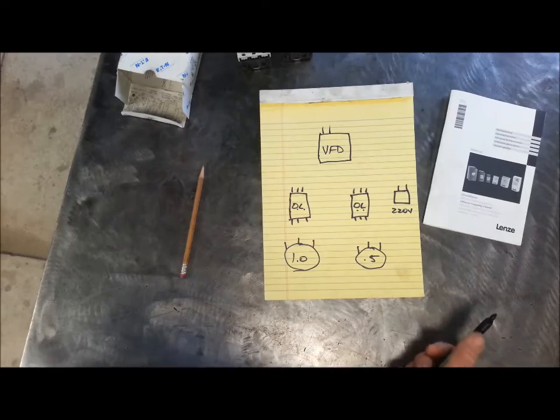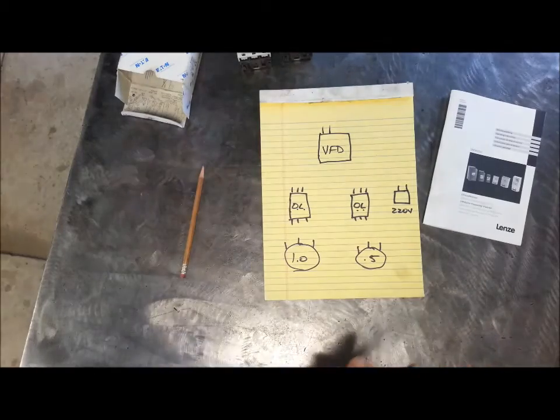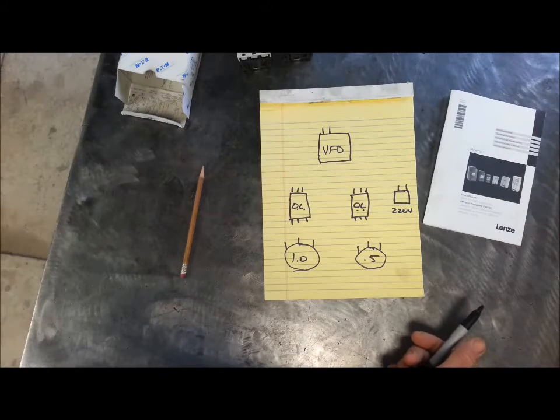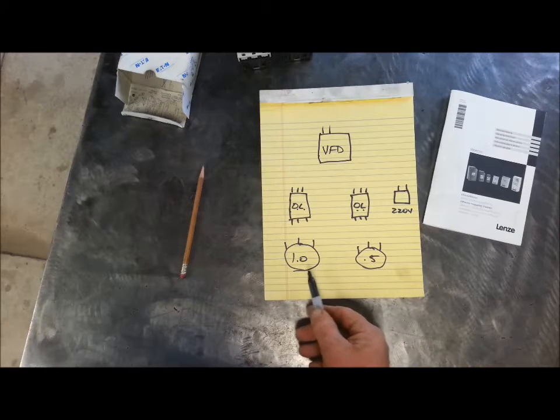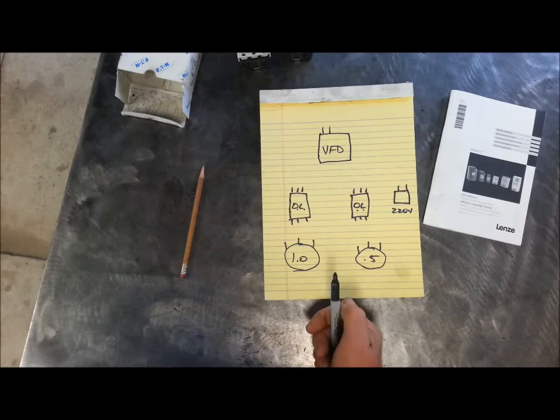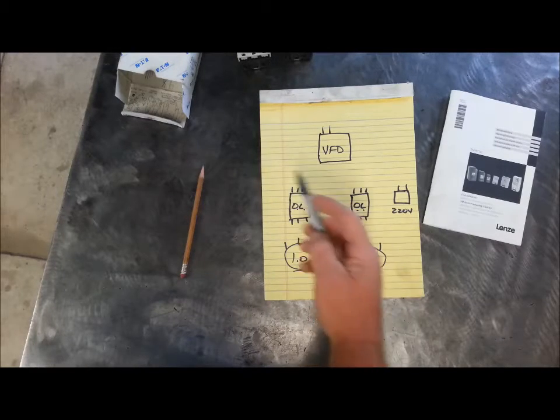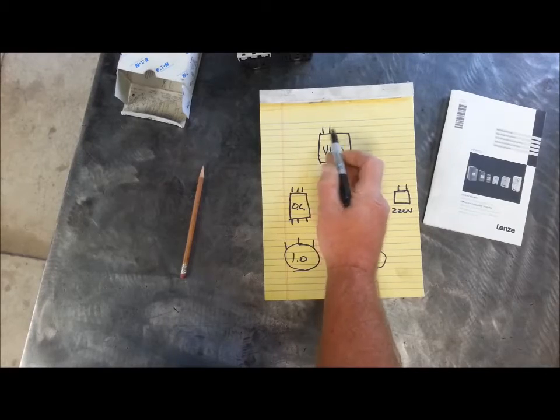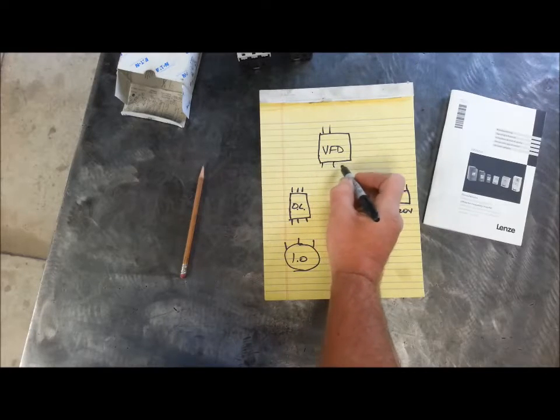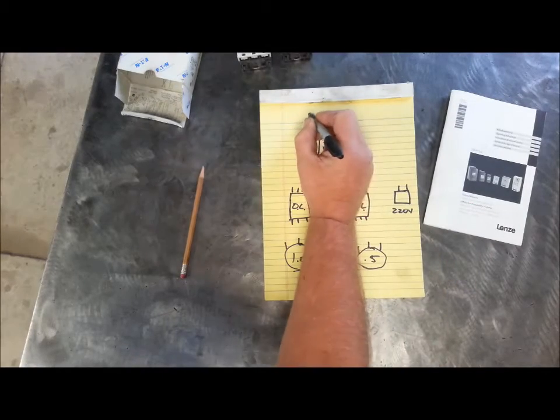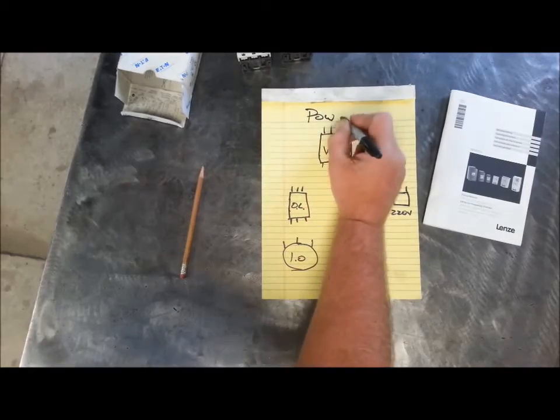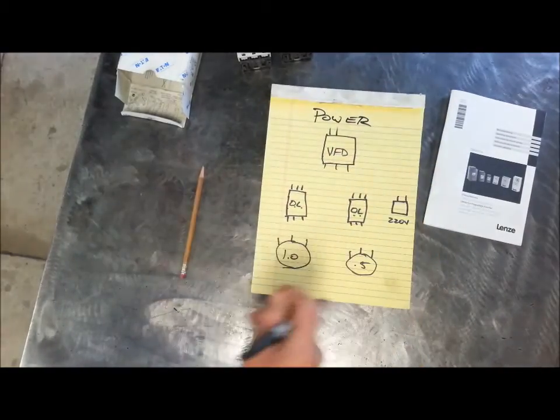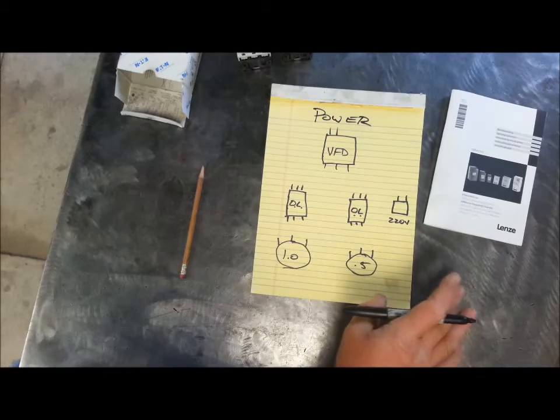AC Tech already has a derating in there. So for this application, I would buy exactly a 1.5 horse drive. But if you choose any other brand, you need to consult that manufacturer. So anyways, we're two phases in, three phases out. And we're going to call this drawing power wiring. Okay, we're not doing any control wiring on here at all.